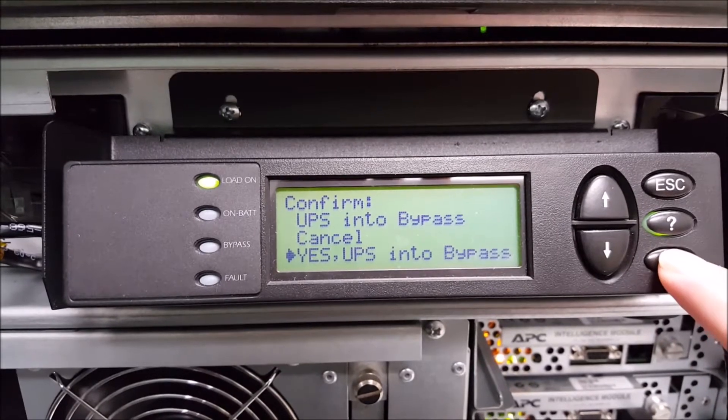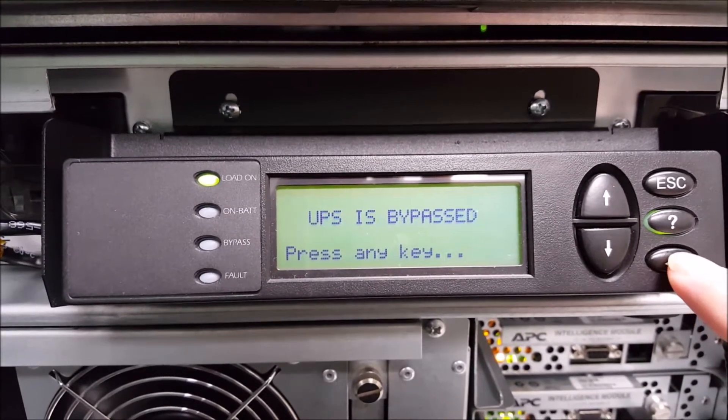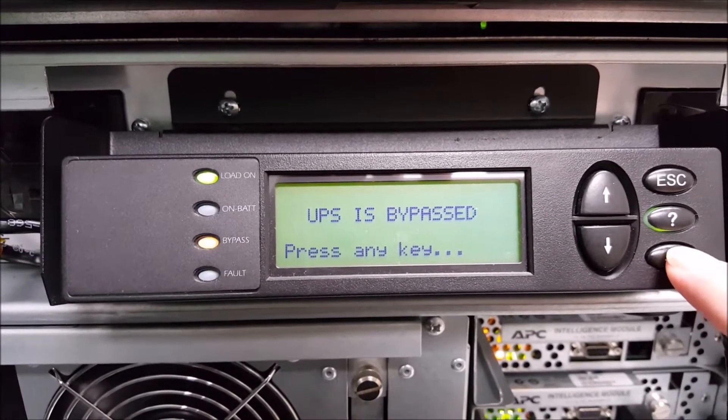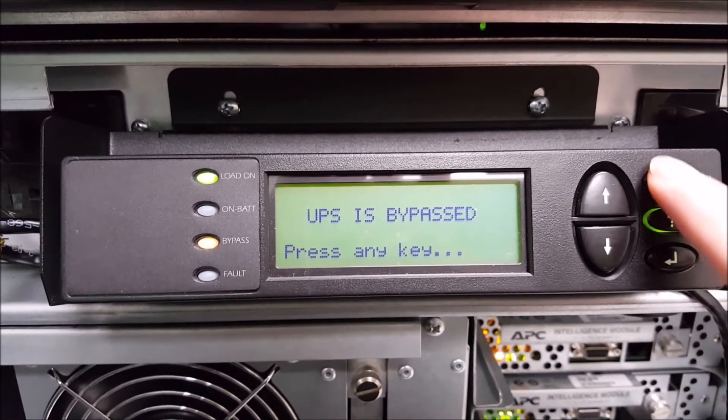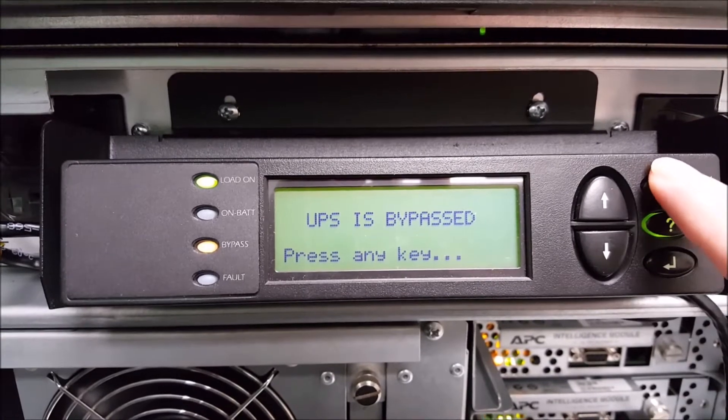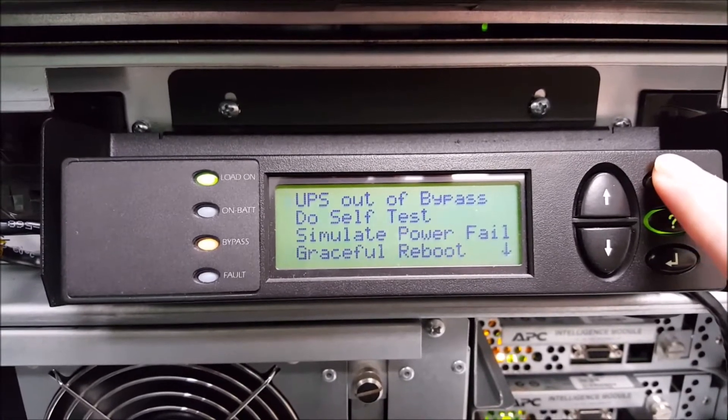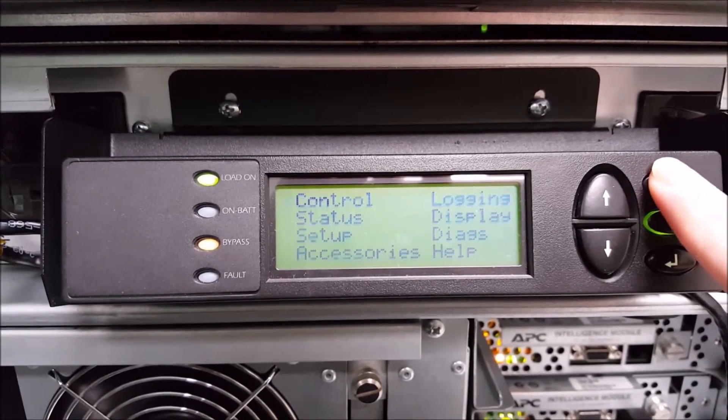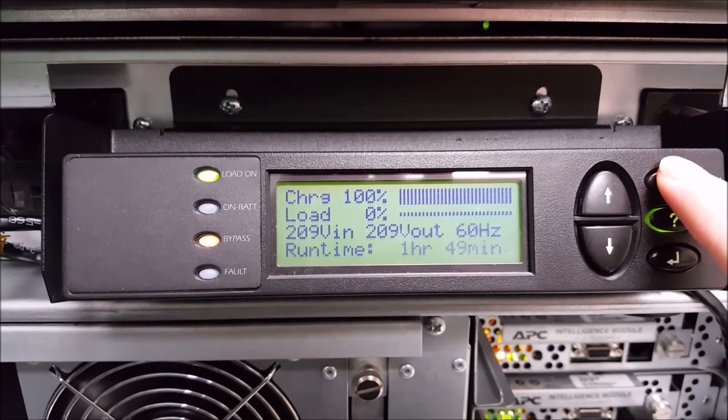If the UPS goes in the bypass properly, you should see the amber bypass light come on. If you get an error message instead, please call technical support before proceeding because you may need further assistance and you might risk dropping your load.